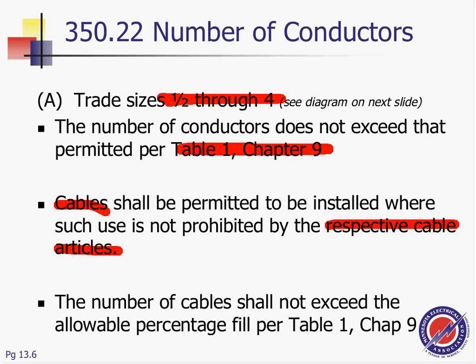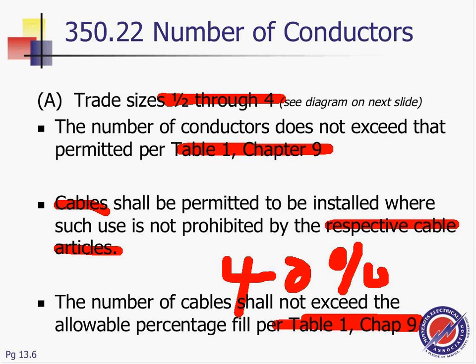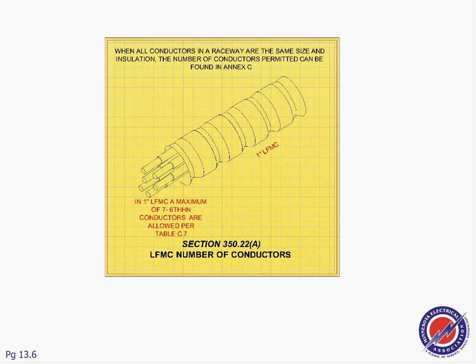Cable shall not exceed, and how much can I fill out of this? Remember that magic number, 40% for all conduits; it also applies here. This is for 350.22, number of conductors, Liquidtight. So you're going to go directly, guys. For example, I have 1 inch. I can put 7 number 6 THHN conductors in that, and this is directly from Annex C. If all the conductors are the same, my friend, then you go directly to Annex C inside them. No questions. The question is about going to Annex C and finding how many conductors of the same size you can fit in this conduit. Not a big deal, huh?